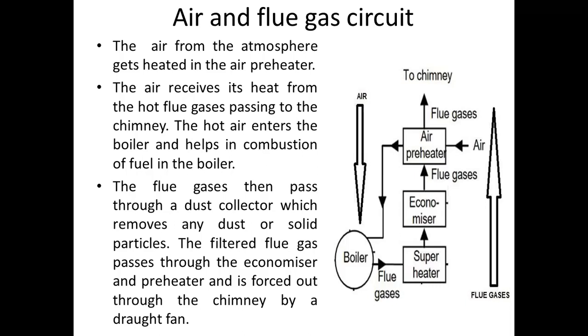The air preheater is a device where we preheat the air which is used for combustion in the boiler furnace. The air is atmospheric air, so whenever we pass this air through the air preheater, the temperature of the air rises approximately by 3 to 5 degrees Celsius. Here the heat of the flue gases is again used. The temperature of the flue gases comes down by approximately 15-20 degrees Celsius.